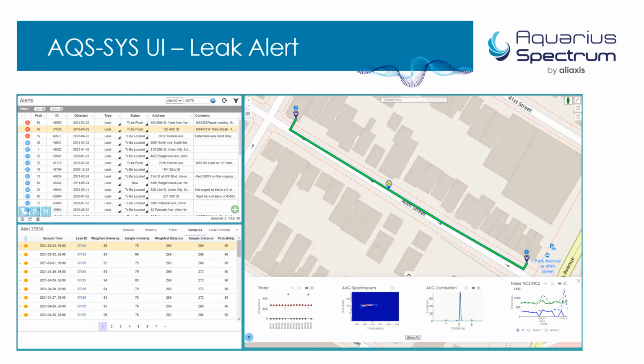This comparison helps to identify irrigations or acoustic phenomena that happen at the time of the recording, which are not water leaks. So it's one of the technologies that is used basically to eliminate or to avoid as much as possible false positives or unwanted acoustic events that happen during the time of the recording.